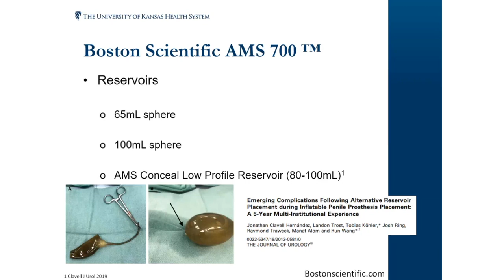And the hypothesis was that if the reservoir isn't filled to at least 80, when it deflates, it can cause the actual balloon to stick together right at the top. And after some use, that will eventually tear a small hole, which leads to complete device failure. So I said to remember the number 80 from the Coloplast devices. If you're using a Conceal reservoir, I would still argue you should fill it to at least 80 milliliters based on this data.